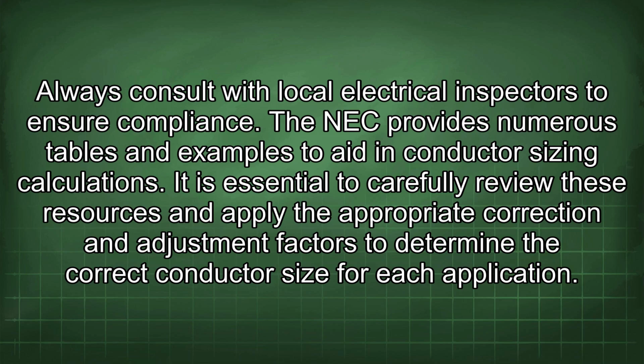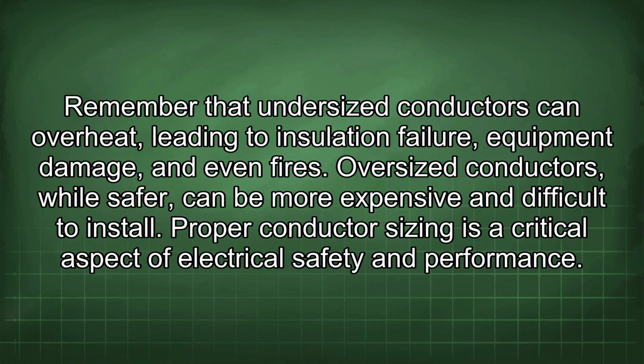The NEC provides numerous tables and examples to aid in conductor sizing calculations. It is essential to carefully review these resources and apply the appropriate correction and adjustment factors to determine the correct conductor size for each application. Remember that undersized conductors can overheat, leading to insulation failure, equipment damage, and even fires. Oversized conductors, while safer, can be more expensive and difficult to install. Proper conductor sizing is a critical aspect of electrical safety and performance.